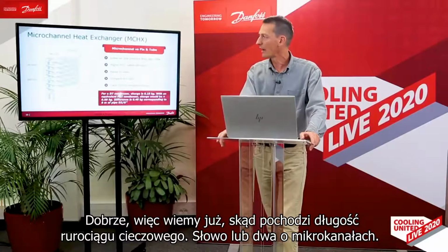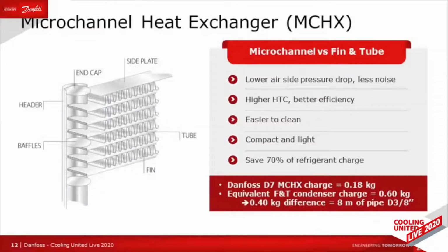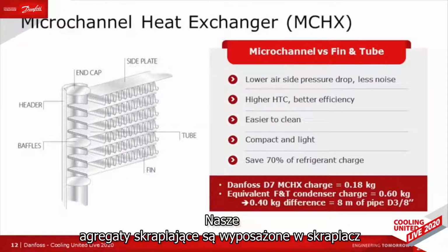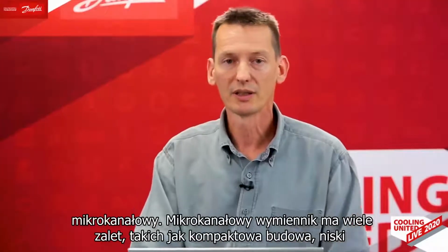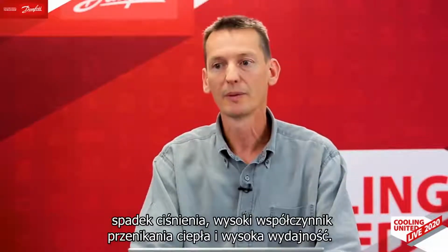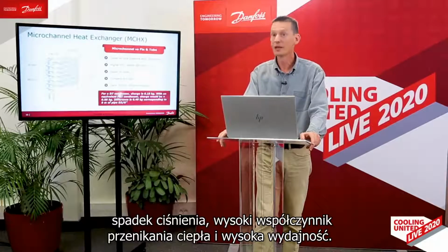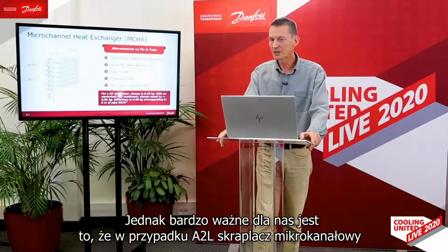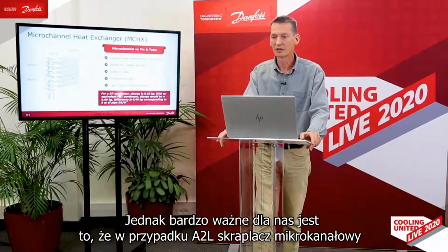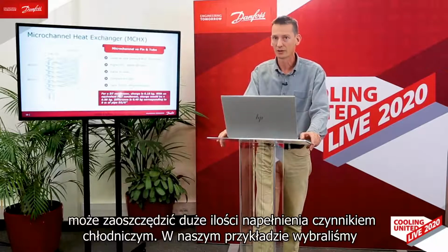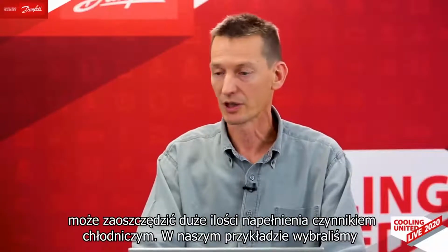A word or two on microchannel. You know that our condensing units are equipped with a microchannel condenser. Microchannel has a lot of advantages, like compactness, low pressure drop, high heat transfer coefficient, so high efficiency. But what is really important for us for A2L is that a microchannel condenser can save a lot of mass of refrigerant.